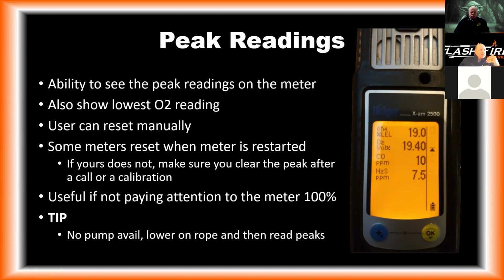So peak readings: the ability to see the peak readings on the meter so we can see how low the oxygen was, how high the oxygen was, and how high the other 3 sensors were as well. We can reset this manually or the meter will reset. It will reset your peaks when you turn the meter off and back on. All right. So I had that if you have a non-Draeger meter, but for us, we don't have to worry about that.